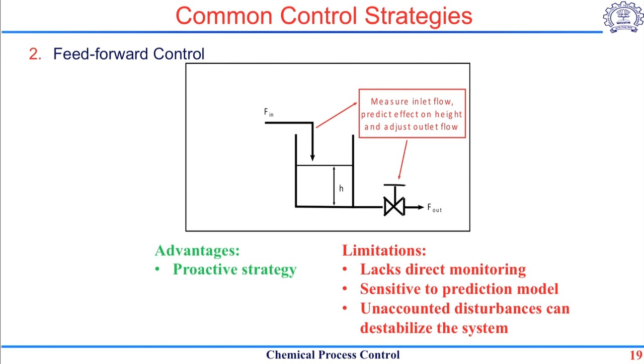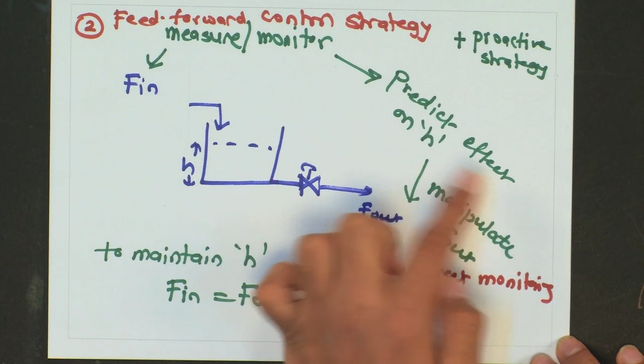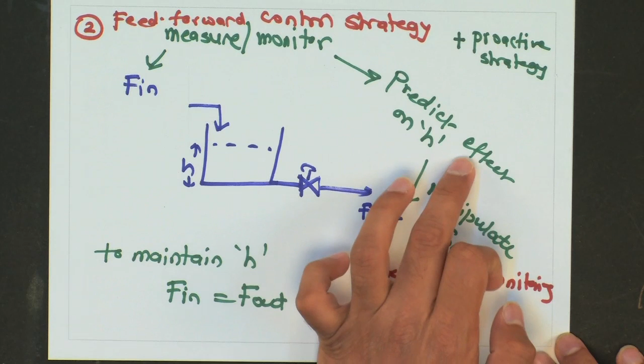Let us now look at what are the limitations of this control strategy. The first and foremost is that it lacks direct monitoring. In this case, all you are riding on is the fact that I am measuring the disturbance and then accordingly taking action, and I am assuming that the controlled variable remains at its desired value. So, it all depends on how good my prediction of the effect of the disturbance on the controlled variable is. If my prediction model is off, then all I am trying to control is a fictitious value of the controlled variable, whereas the actual controlled variable may be away from its desired value, but we are not measuring the controlled variable, and so we would not know that it is not at its desired value. So, the main disadvantage of a feed forward control strategy is that it lacks direct monitoring, and riding on the same fact, it is also not robust and it is very sensitive to the prediction model.